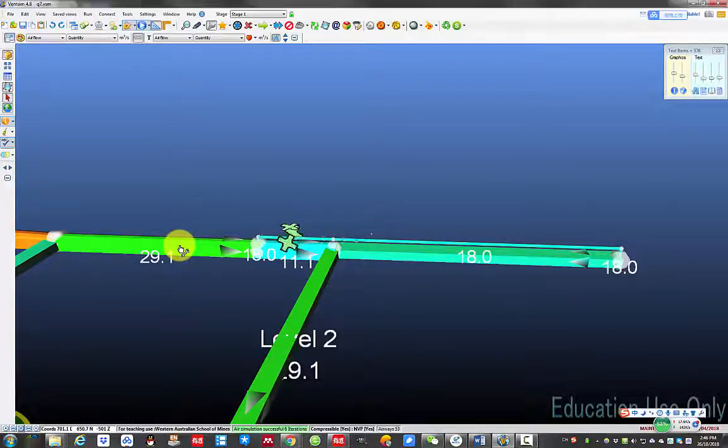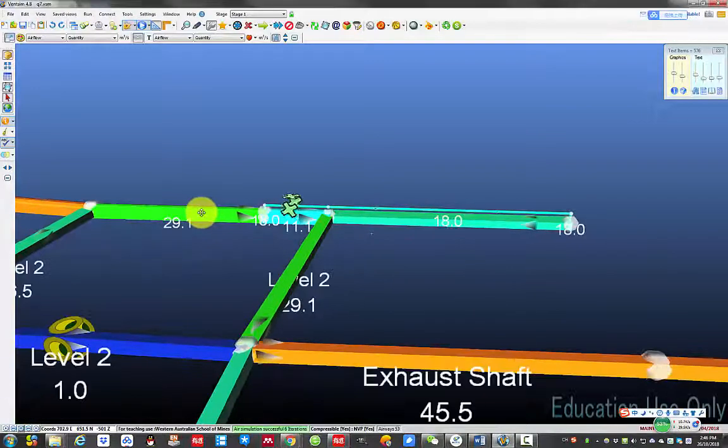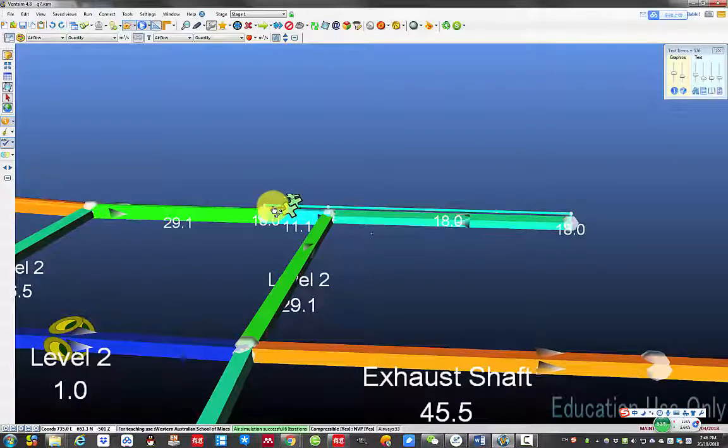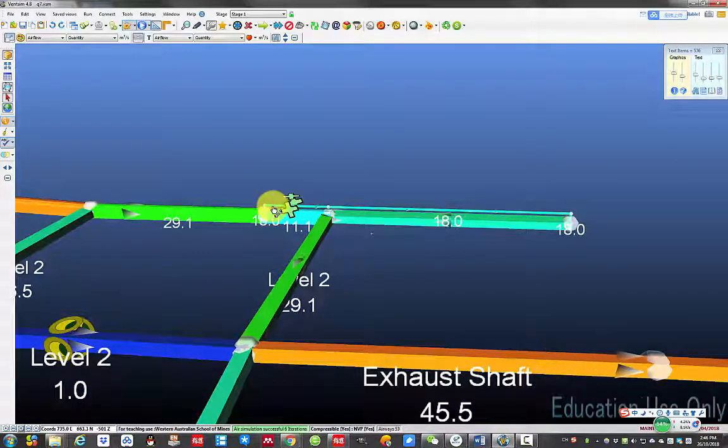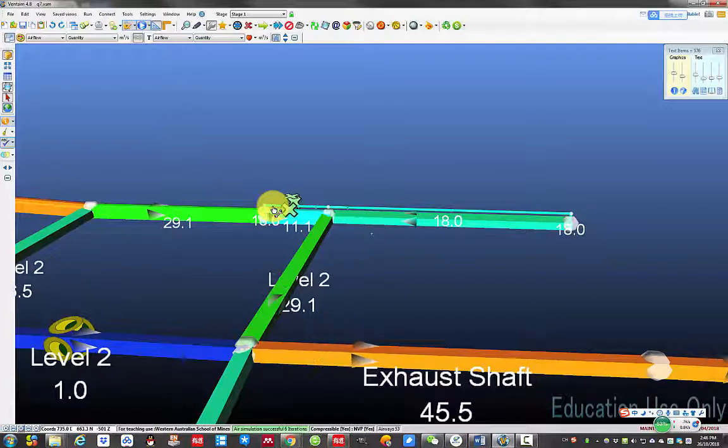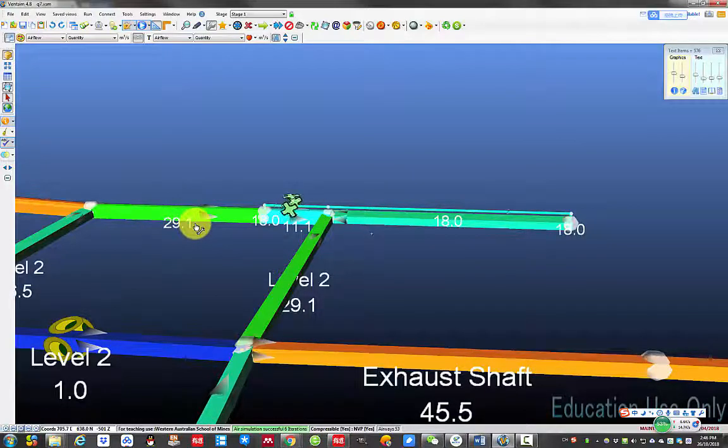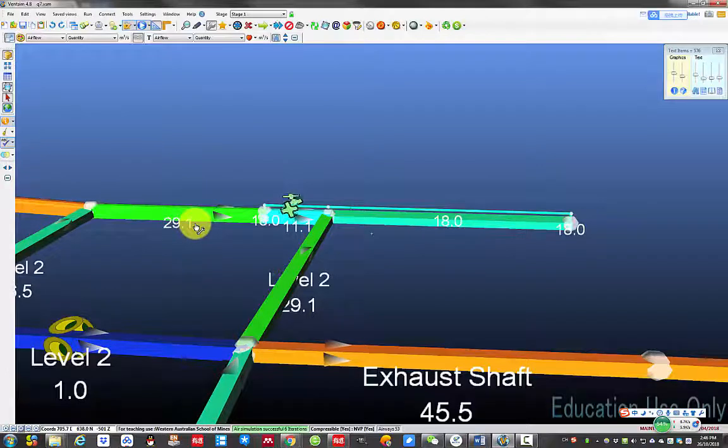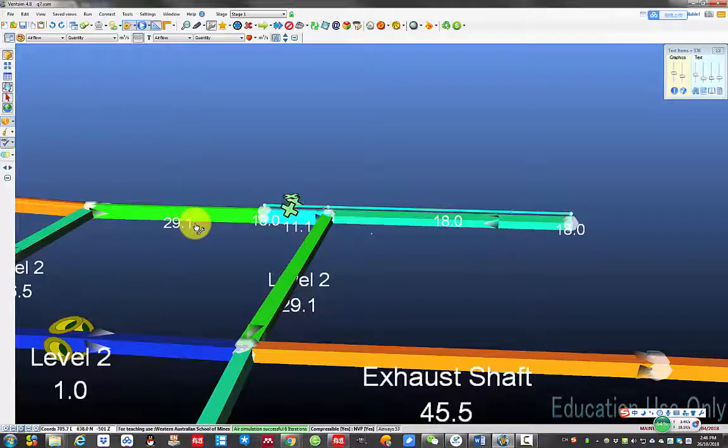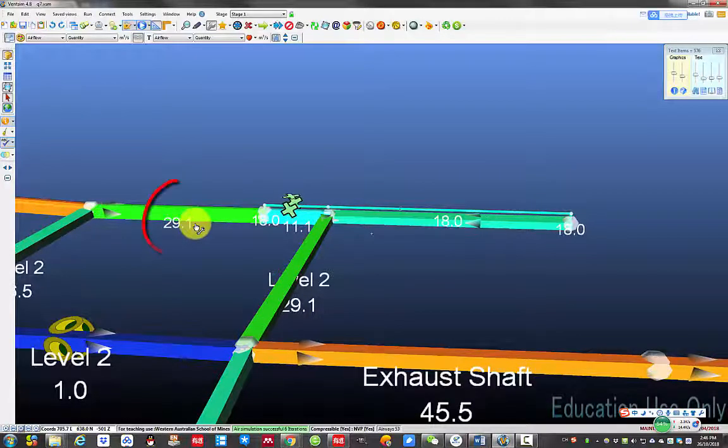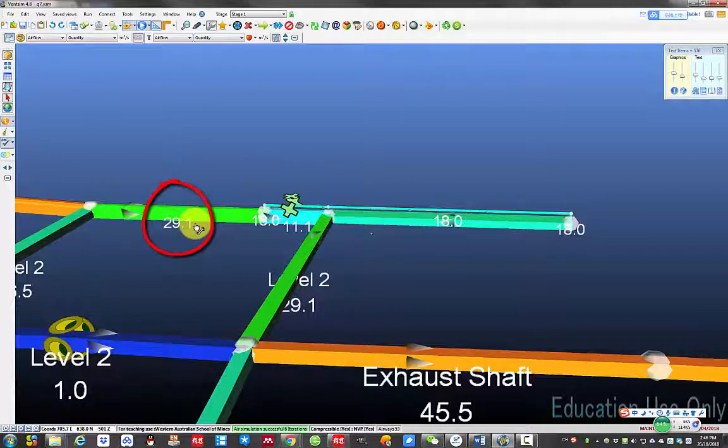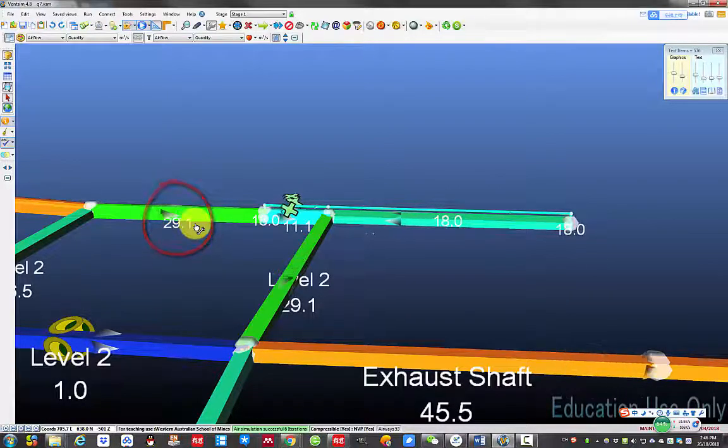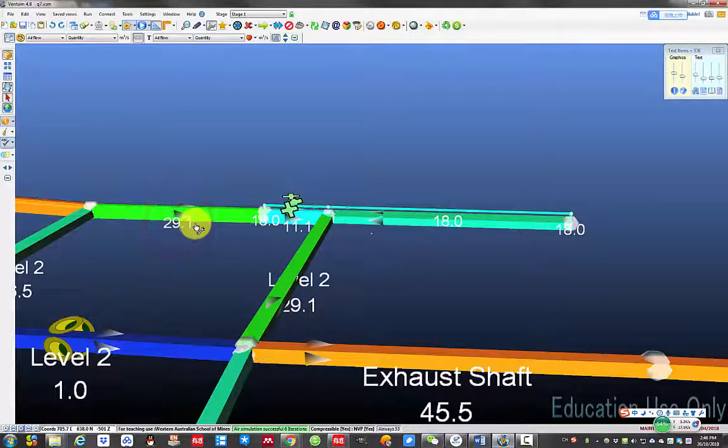In this example, you need to provide 18 cubic meter per second of air, thus need to make sure the airflow in the airway is larger than 1.3 times of 18, which is 23.4 cubic meter per second. We have 29.1 cubic meter per second of air in the airway, thus it is okay.